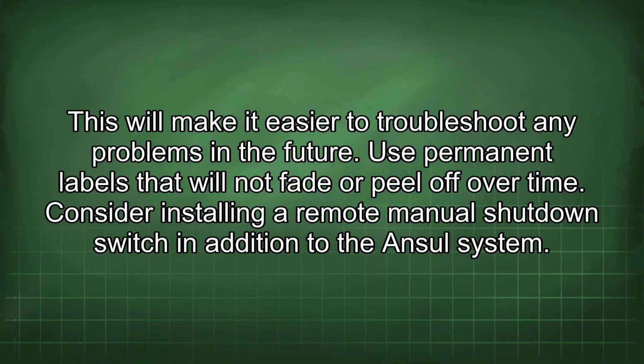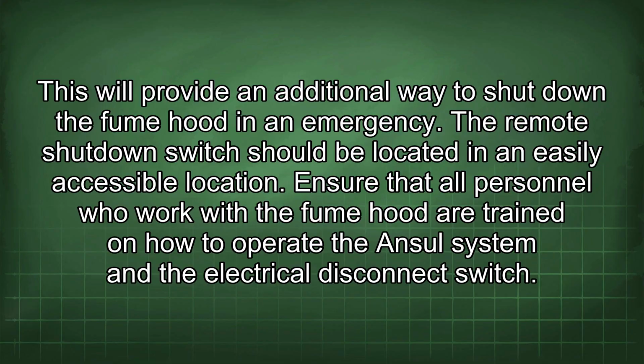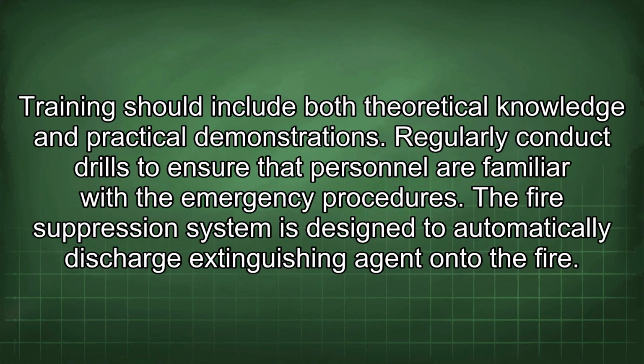Consider installing a remote manual shutdown switch in addition to the Ansul system. This will provide an additional way to shut down the fume hood in an emergency. The remote shutdown switch should be located in an easily accessible location. Ensure that all personnel who work with the fume hood are trained on how to operate the Ansul system and the electrical disconnect switch. Training should include both theoretical knowledge and practical demonstrations. Regularly conduct drills to ensure that personnel are familiar with the emergency procedures.